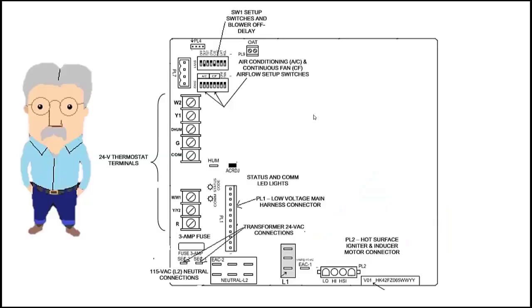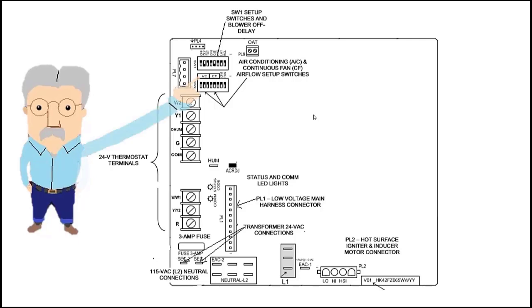All gas furnaces have a circuit board inside, and they control several functions. But the biggest function they control is the sequence of operation. Let's take a look at this circuit board real quick. Up here we have a set of dip switches, and these primarily control the blower speed, its delay, whether there's air conditioning, the continuous fan, and airflow setup switches.